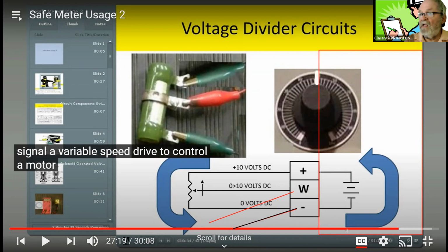See, on the input to your VFD, it looks at what that voltage is. If it's 10 volts, it tells the drive that the operator turning that knob is asking for 10 volts. If you start bringing it down to the bottom side, then it's going to start reading 0 volts. So up and down, you're going to see 1, 2, 3, 4, 5, 6, 7, 8, 9, 10. This here communicates to your VFD.